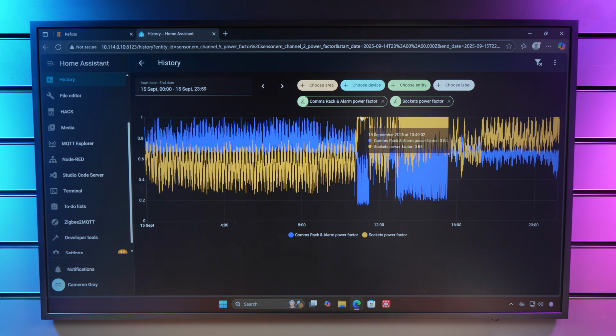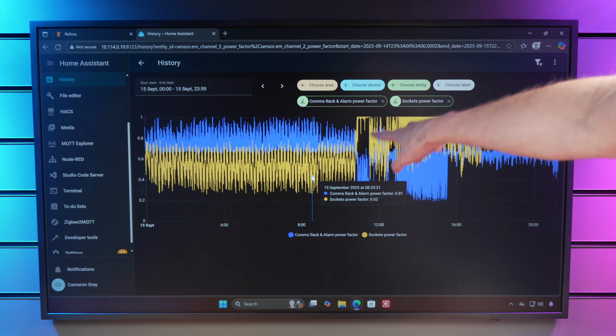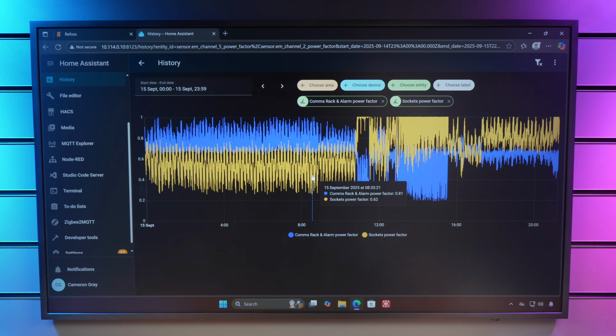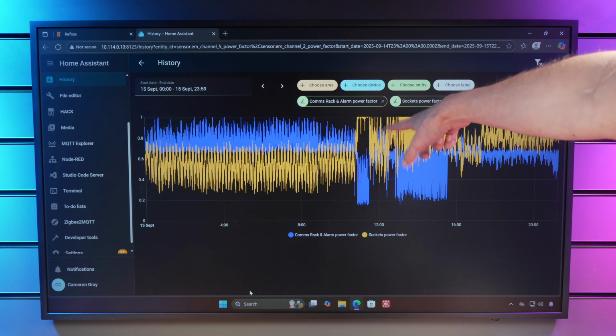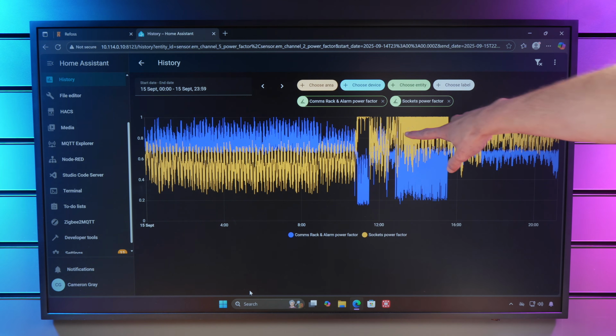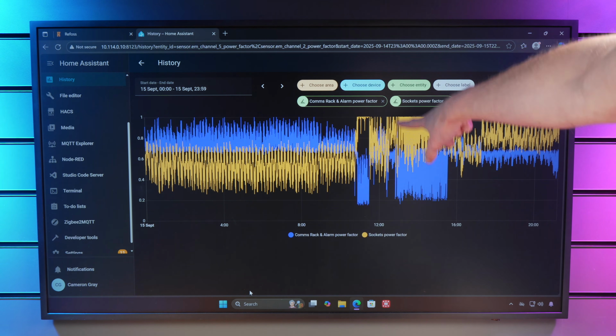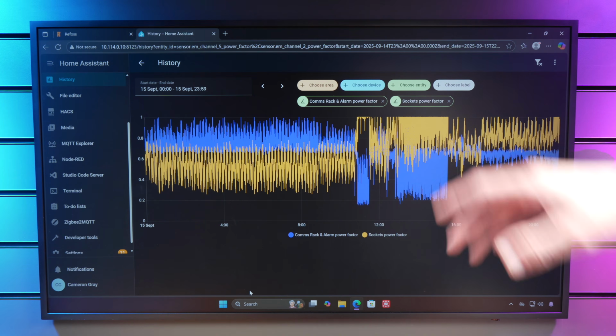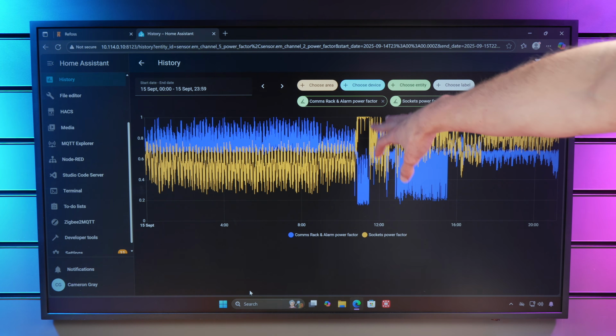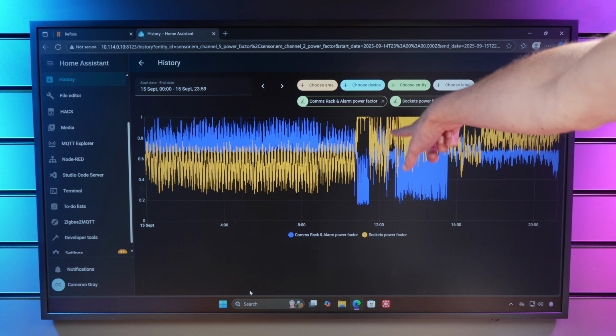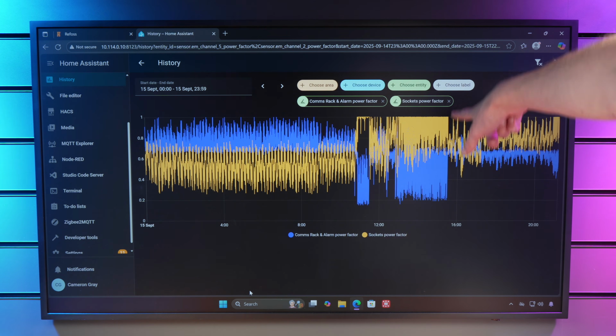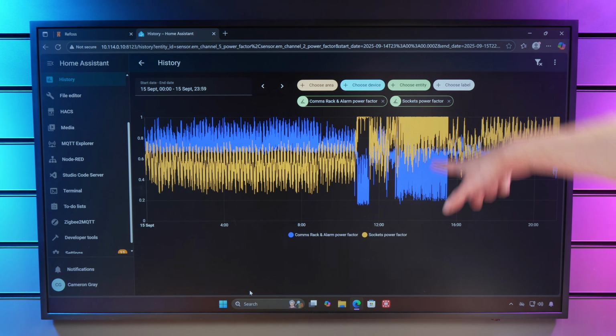Heating element kicks on, and the power factor for the socket circuit goes up very close to 1. Then it fluctuates a little bit around here. This is probably when the wash cycle was going on, the heating element wasn't being used as much. Then it switched into the dry cycle, and once again, the power factor for the socket circuit jumped right up. A lot more fluctuations here than before. I suspect maybe when it's in the drying cycle, it turns the element on an awful lot more, or maybe modulates it somehow. But once again, you can see when the heating element's kicked in, the power factor tracks a lot closer to 1, and then drops down again when the machine finished its cycle.